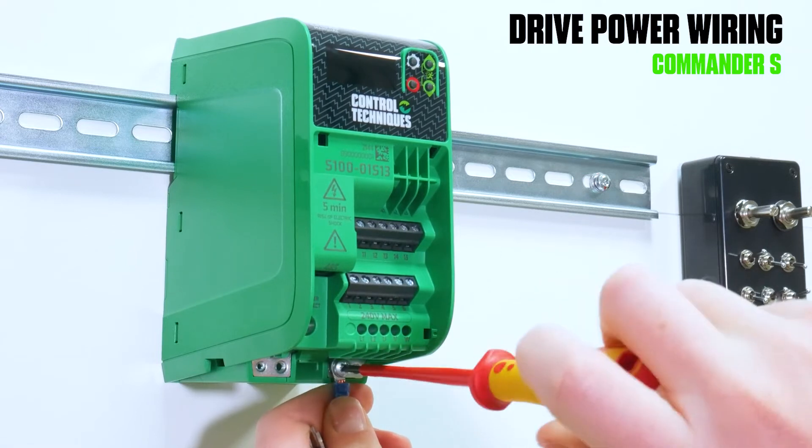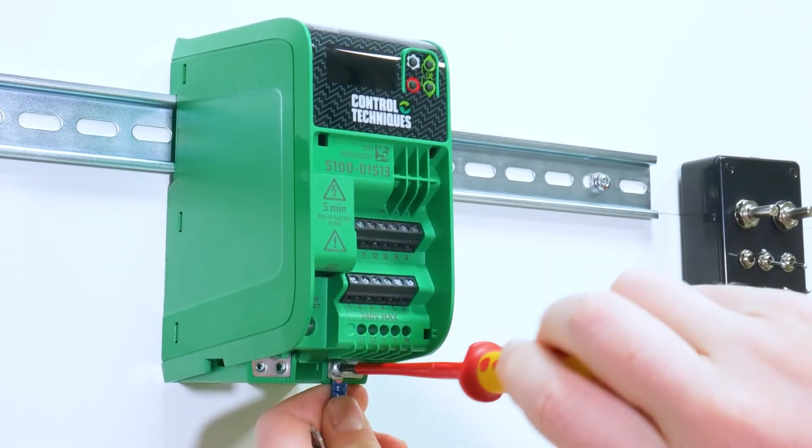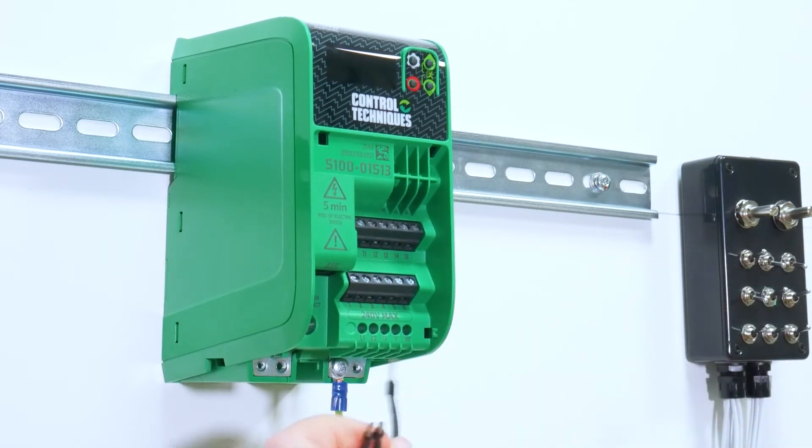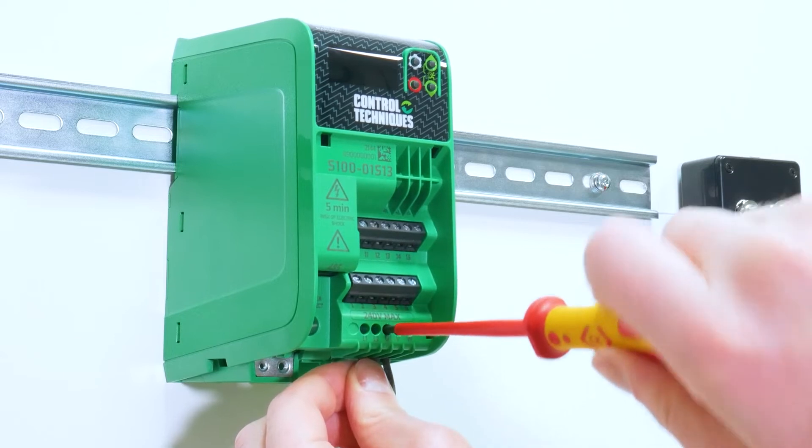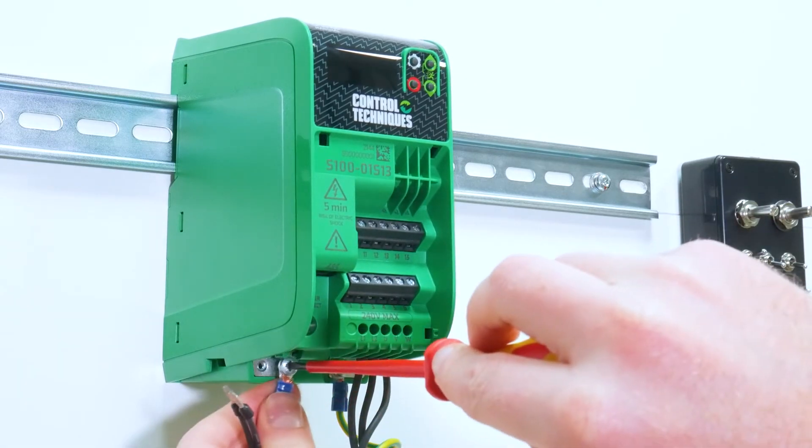Step two is to wire your drive. Start by connecting your motor earth, followed by your motor phase cables, then your supply earth.